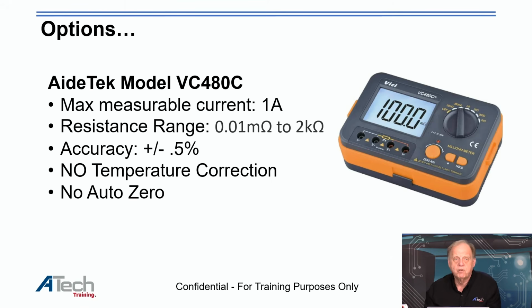We go to our next one up here, and it's AideTek. And this one is a VC480C. There are other ones out there on the market. This one has, again, the current's 1 amp. That's pretty standard across. I have 0.01 milliohms up to 2K ohms, so its range is not as good. Accuracy is not there. It's at 0.5. Notice the other one's at 0.0 something. This one is at 0.5. It has no temperature correction and has no auto zero. The temperature correction is probably more important than the auto zero in the process on this, but these are some options you might have looking at some meters you might want to purchase.